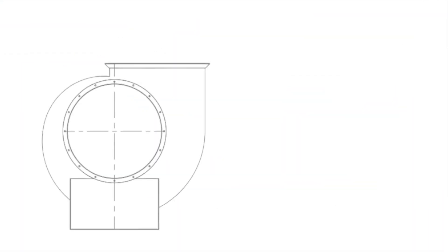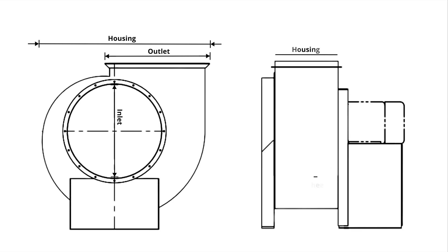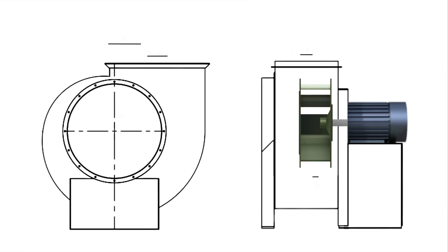Backward inclined fans get their name from the blade's backwardly inclined orientation relative to the wheel's rotation. These fans generate medium to high amounts of airflow at low to medium amounts of pressure. Capable of efficiencies of 80 to 90 percent, backward inclined fans are the most energy efficient of the centrifugal fan types. Some characteristics all backward inclined fans have in common are large inlet and outlet openings relative to casing size and wide casings relative to wheel width. In general, backward inclined fans are vulnerable to material in an airstream because material tends to build up on the back side of the blades, which can cause imbalance.